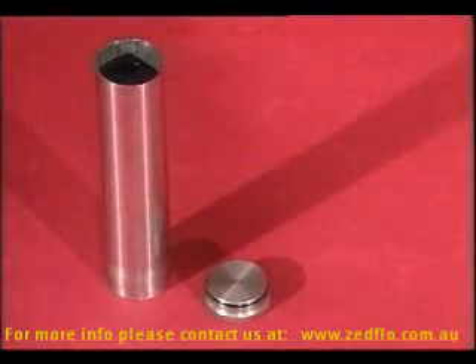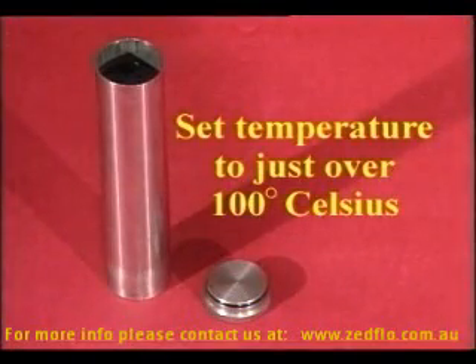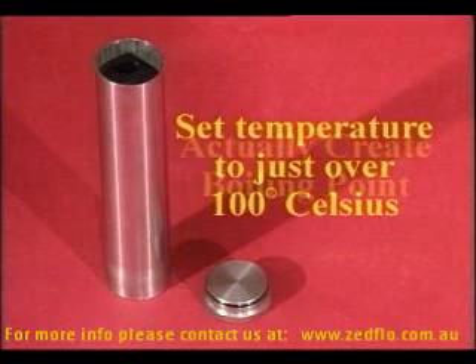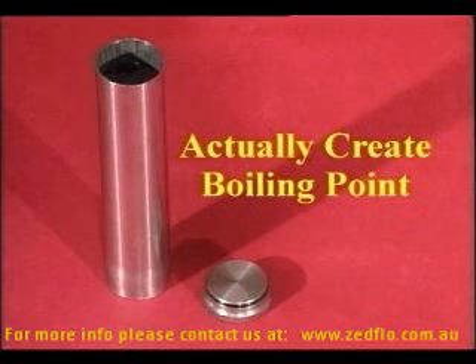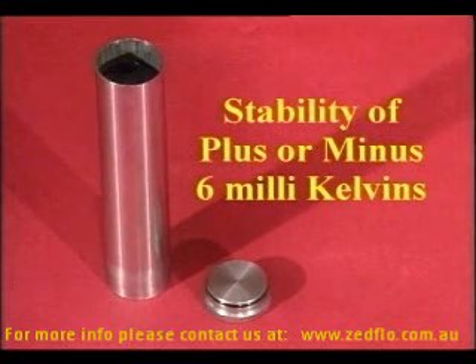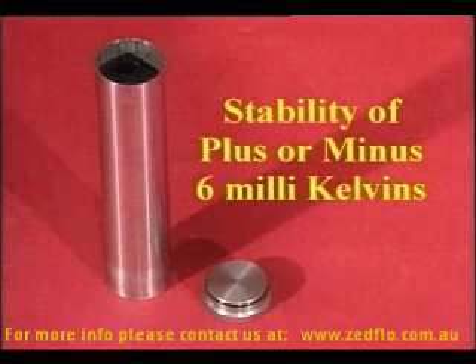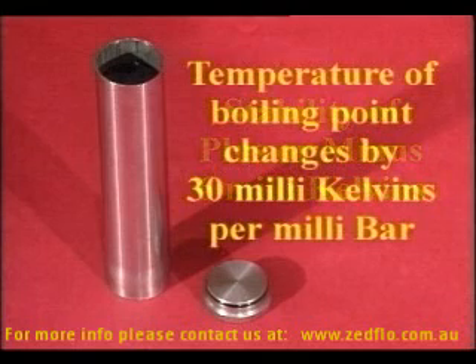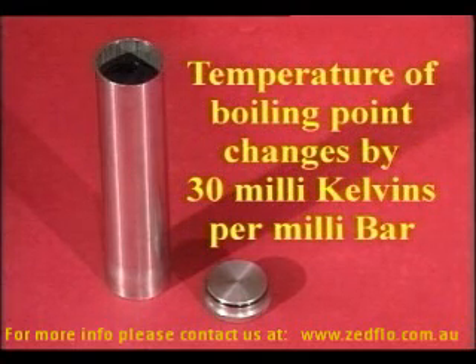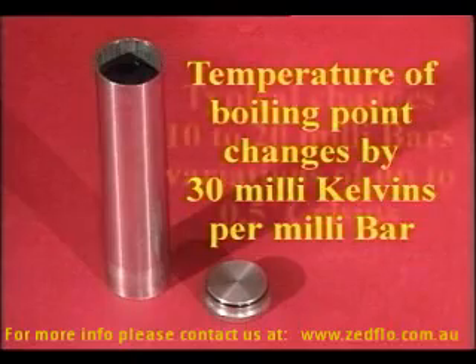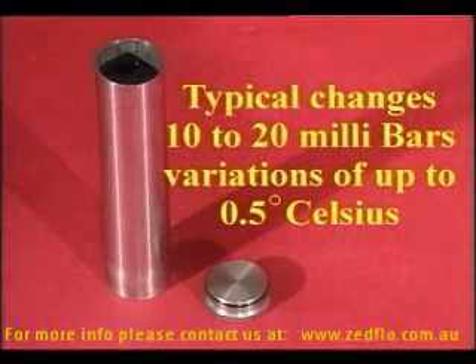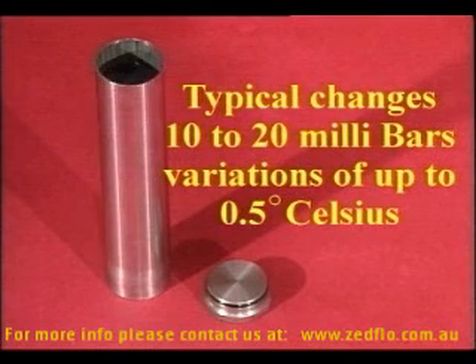But that's not all this little stirred liquid bath can do. It can set the temperature of any of the Isocal 6 baths to just over 100 degrees Celsius. Fill the liquid container with water and actually create boiling point. A similar chart recording is available. It shows the stability of about plus or minus 6 millikelvins at the boiling point of water. The problem with the boiling point of water is that you need to know the pressure very accurately, as the temperature of boiling point changes by about 30 millikelvins per millibar. Here at Southport, we can get changes of typically 10 or 20 millibars, and this means variations of up to half a degree.